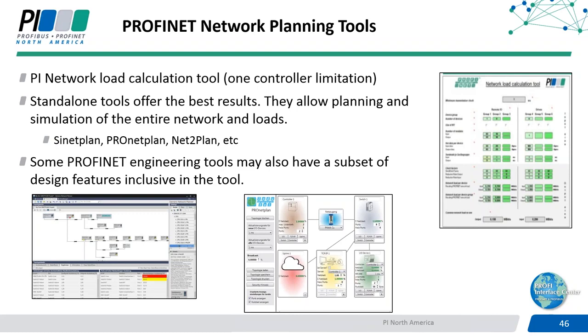Then you can get a good calculation of what your load's going to be at those critical points, without having to go out there, install everything, and find out the hard way later that you've got problems. It should also be noted that some PROFINET engineering tools have a subset of these design features built in. So as you're adding devices, or viewing the topology, it'll automatically calculate what the maximums and minimums can be, and whether the topology is going to work. Usually if something's wrong when you compile your project, you'll get an error warning saying you have too many devices in this line topology for this particular update time.